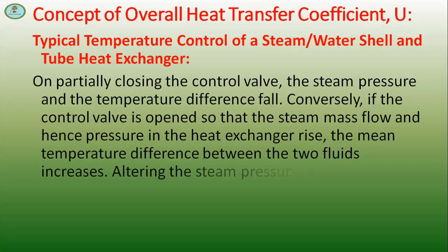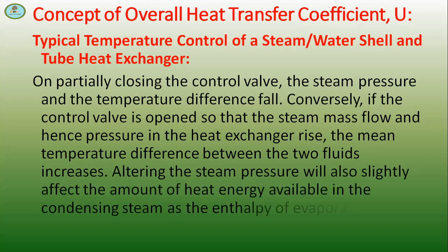Altering the steam pressure will also slightly affect the amount of heat energy available in the condensing steam, as the enthalpy of evaporation actually falls with increasing pressure. Temperature design constant.